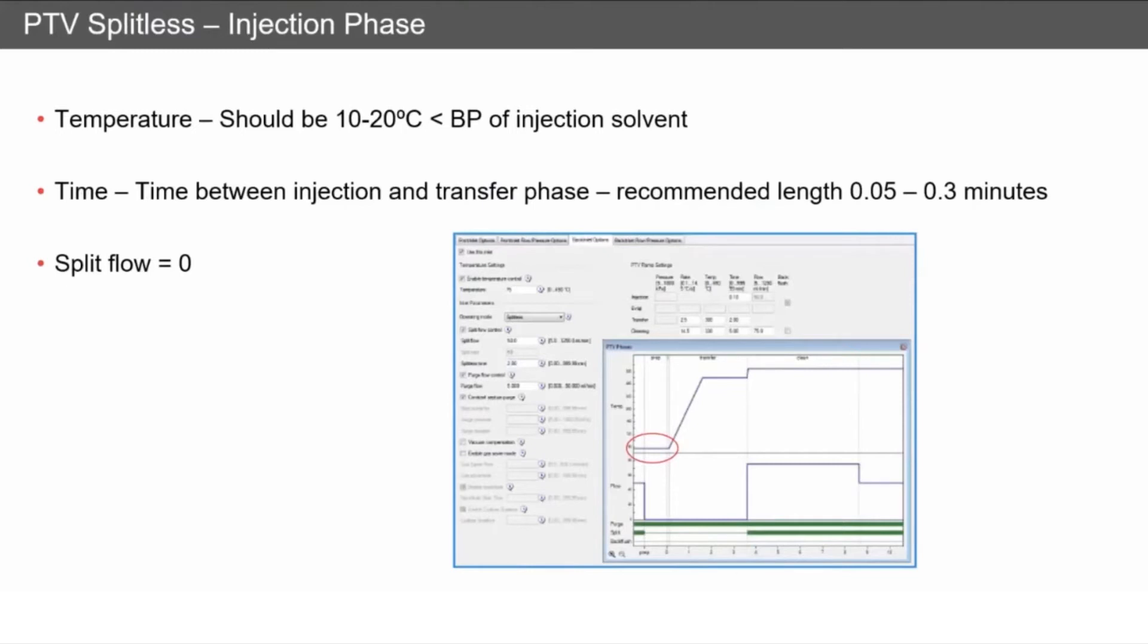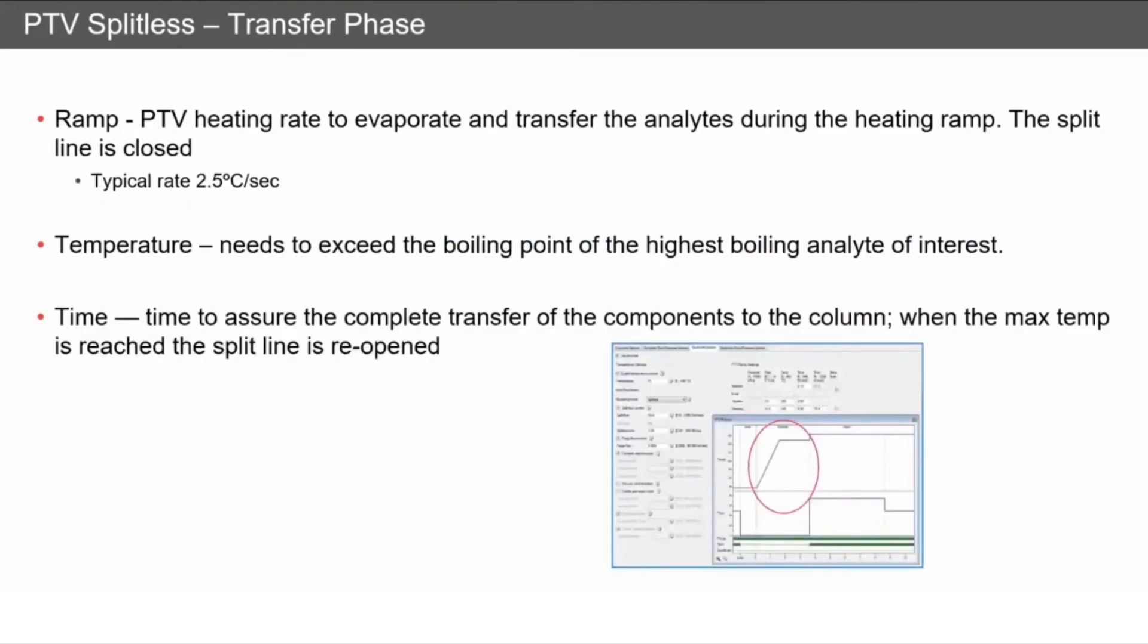Now we're going to transfer everything to our column, so we're going to ramp up the inlet while the split line is closed. It's really important that this rate is controlled. Typically, I'd recommend 2.5 degrees per second. The temperature needs to exceed the boiling point of the highest boiling analyte of interest. So if your highest boiling point analyte is 260°C, we need to go up to 280-300 degrees to make sure it's evaporating and transferring onto the column.